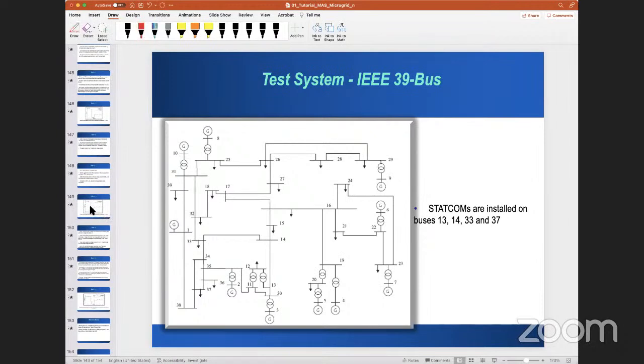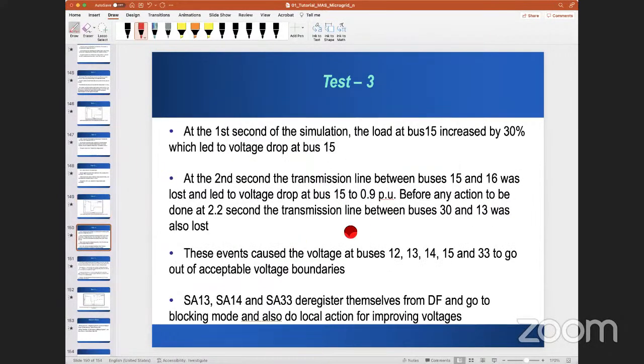Okay, so 159 here. 13 and 30, so two lines out. And then we have voltage much below the bus 15 voltage, much below the 0.9 per unit, much below the lower limit. This event caused the voltage at buses 12, 13, 14, 15, and 33 to go out of acceptable voltage boundaries. So not only bus 14, but many other buses are seeing the violation.